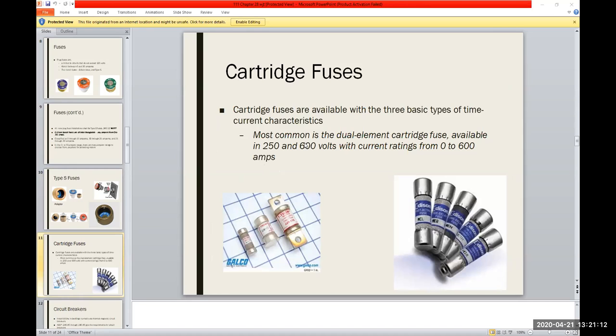A lot of them are in little sockets, if you will, where they're press fit in with spring clips. And if you look down in the picture here from Galco, the biggest size over there does have a screw-in style, and you will run into those if you get out in an industrial setting. You'll run into those on certain circuit panels. They'll have them cranked down, in like the 480 lines and whatnot. They typically use those style fuses where they're clamped down, no spring socket or anything like that.